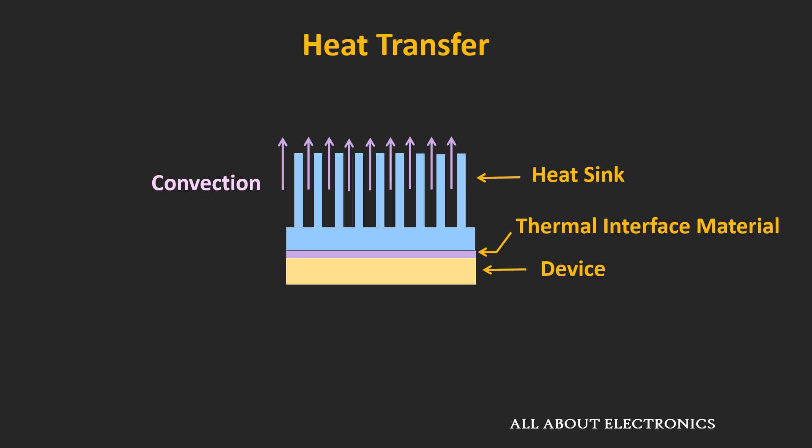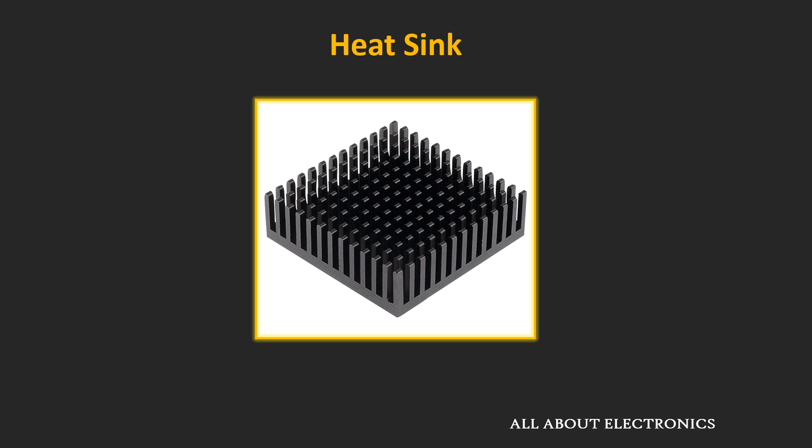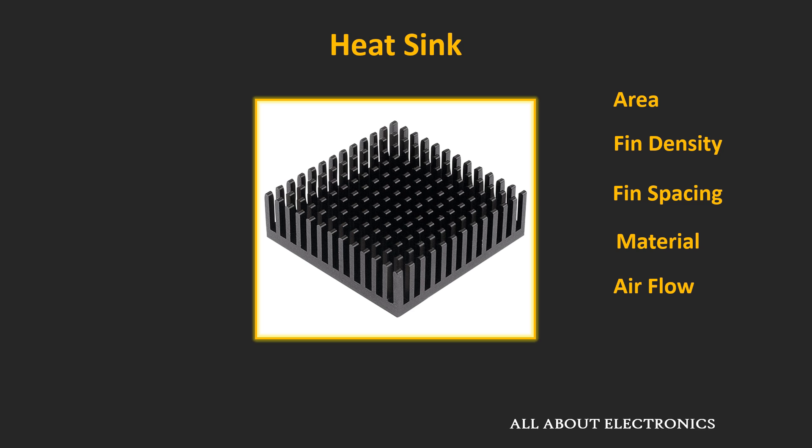The heat sink is designed so that the surface area in contact with the cooling medium is maximized. The idea is that the contact area of the heat sink should be at least 10 to 20 times more than the surface area of the device, which is why this fin-type arrangement is used. The performance of the heat sink — how well it transfers heat — depends on multiple parameters: the area of the heat sink, the fin density, the fin spacing, and the material used. Usually either aluminum or copper is used for construction.